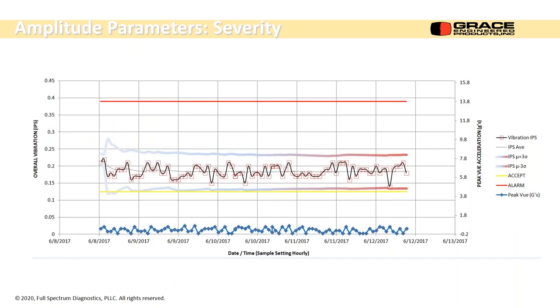And when we're looking at amplitudes, here's something I brought up on Tuesday. I'll do a little more of this next Tuesday. But this is some sampling and some statistics on just 4 days of data from a power plant. So this was a big vertical pump. I have a bunch of statistics in here, but I'm looking for an alarm criteria. And what I have is a value that's changing the more data I get. As I'm taking data, I'm adding to my statistical population. And once I get out here 4 days later, my alarm criteria has gone down here and it's squeezed in there.